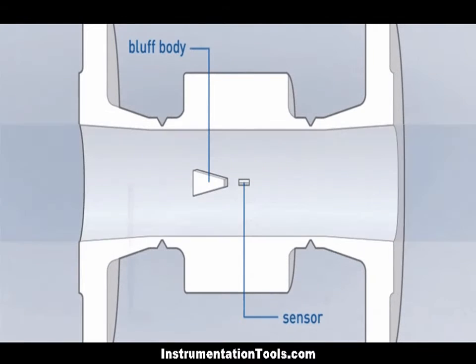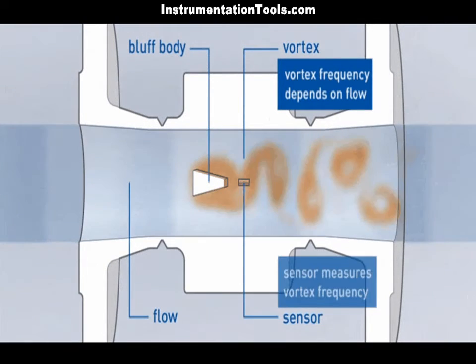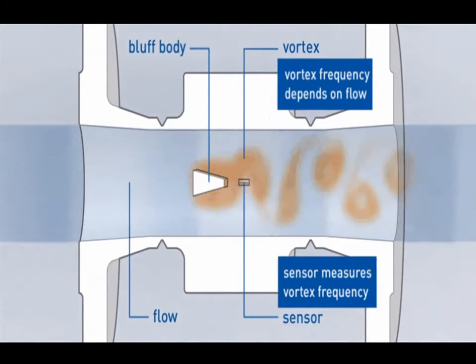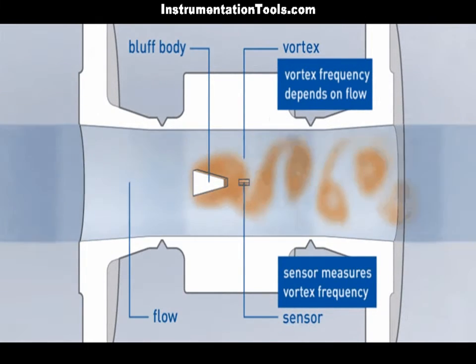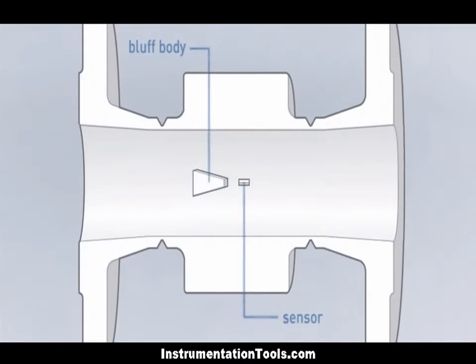A vortex flow meter works based on the principle of Karman Vortex Street, demonstrated in the above figure. This principle essentially means that when an obstruction is placed in the path of a flow, it produces a series of vortices alternating from each side of the obstruction. The frequency of alternating of these vortices is proportional to the flow rate being obstructed.